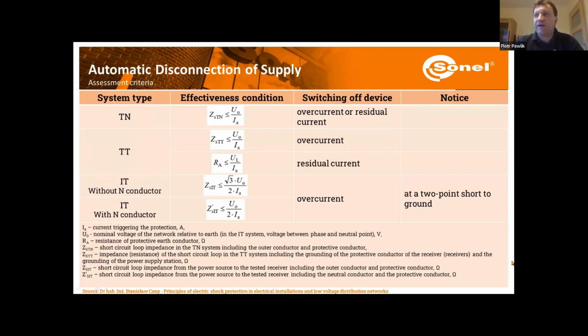Okay, so to summarize the automatic disconnection of supply, here we can see the conditions to check the effectiveness. So in case of a TN network, we measure fault loop impedance, we calculate the fault current, and fault current should be higher than the current triggering our breaker within the time described by the standard. So again, this could be MCB, RCB, or some bigger breakers. Now, in case of a TT system, when we have the overcurrent protection, that's the same as in case of a TN. And when we have the RCD protection, then we need to check the earth resistance of the earth electrode and the resistance or the continuity of our protective wires in the wall, and multiply them by the rated current of the RCD, and this value should be lower than the long-term permissible voltage, so the 50 volts.